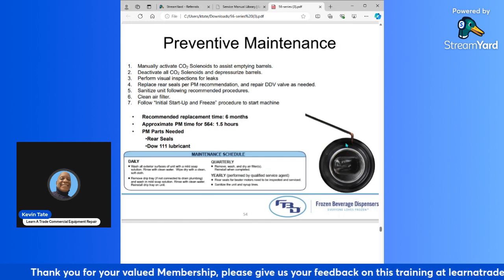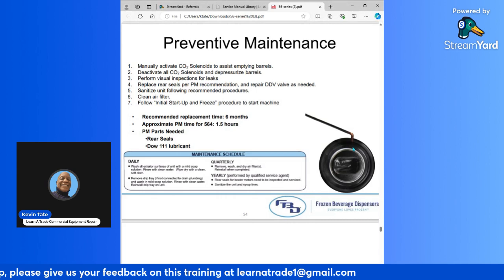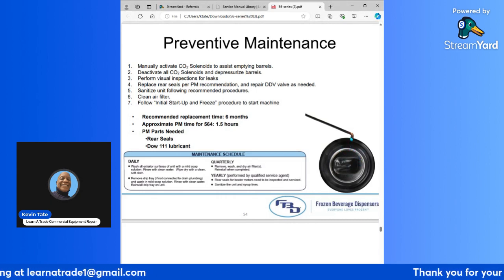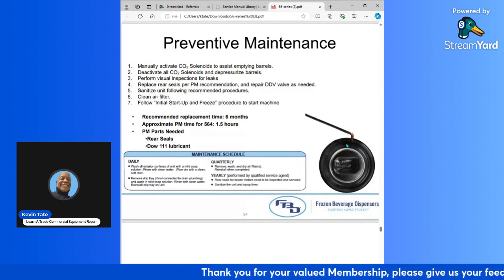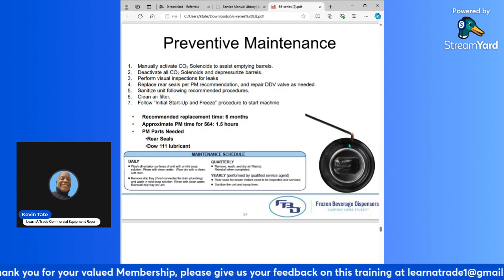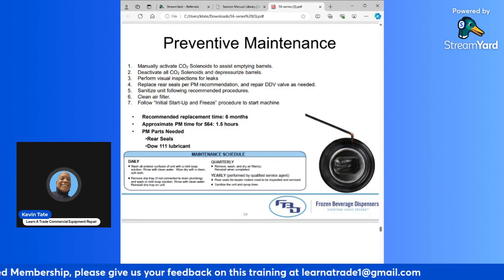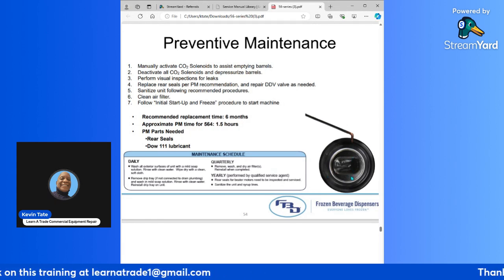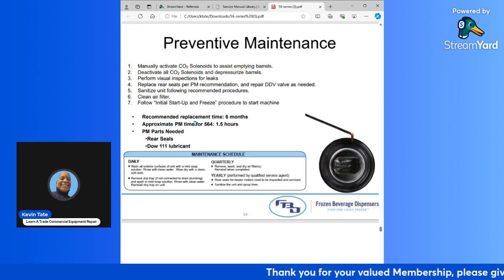So that rear seal they were talking about, you can see they have a pick here. You would use a pick, and that is in the rear of the barrel. So you would have to reach your arm in there with the pick, and then you'll dig your pick into the rubber material of the seal, and then you should be able to get enough of the pick in there to pull that seal out of the barrel, and then you'll replace it with a new rubber seal. And then they recommend replacement of these seals every 6 months.